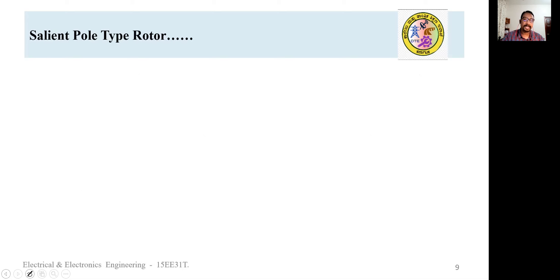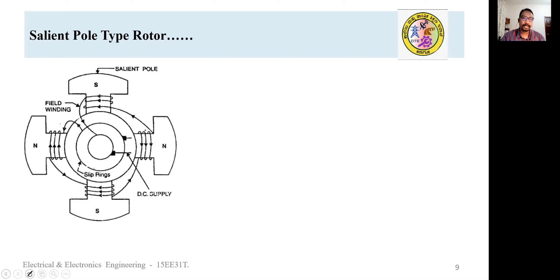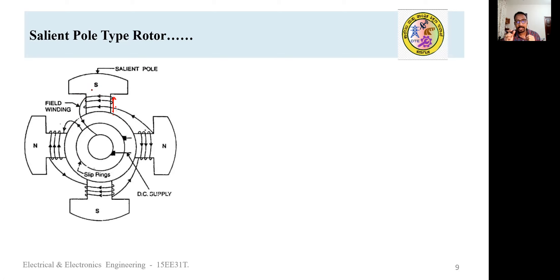For the salient pole type rotor, observe the constructional details: the poles project outward from the magnetic drum — hence it is called salient pole. The main characteristic of the salient pole type rotor is that it has a large diameter and a short axial length. On the cores of these projecting poles, the field windings are placed.